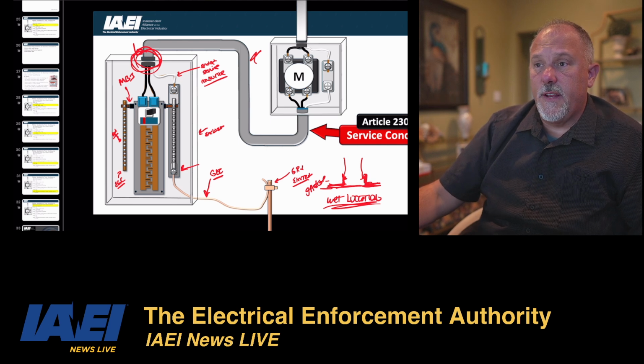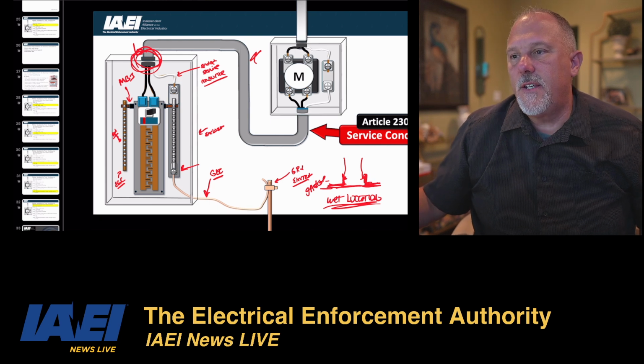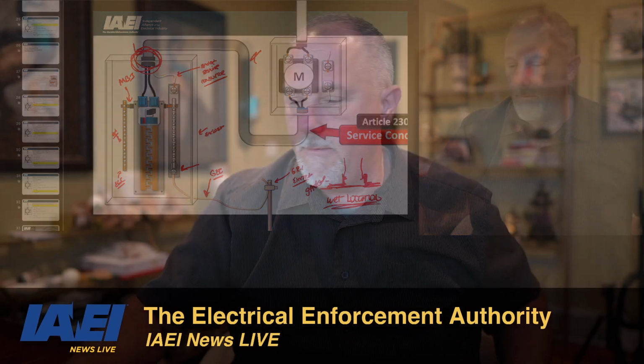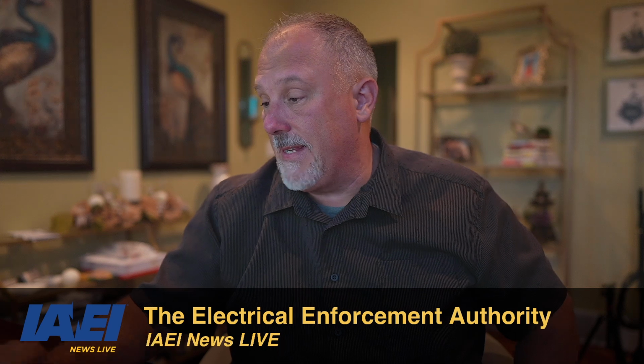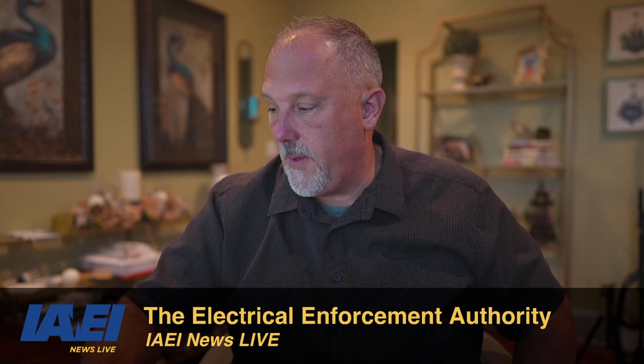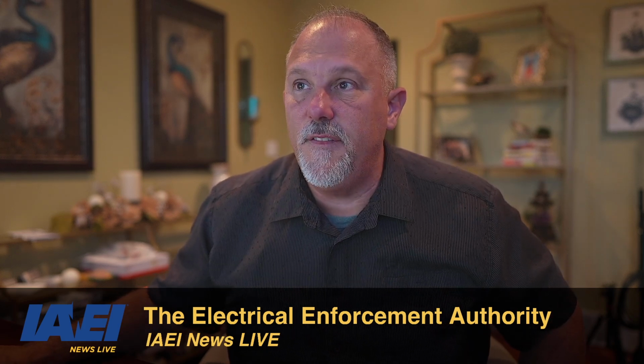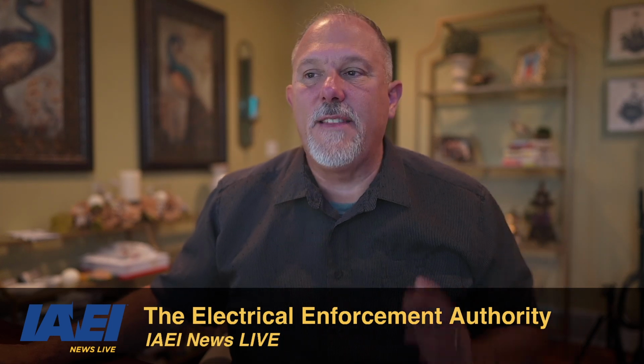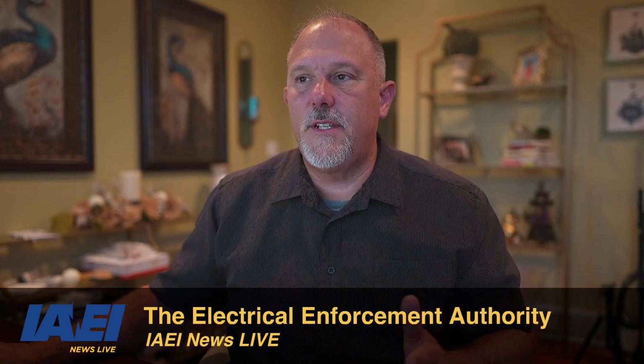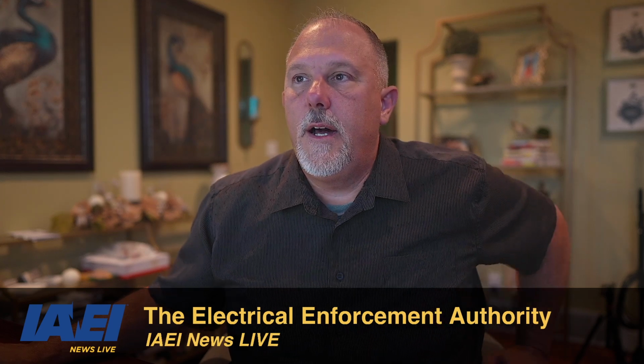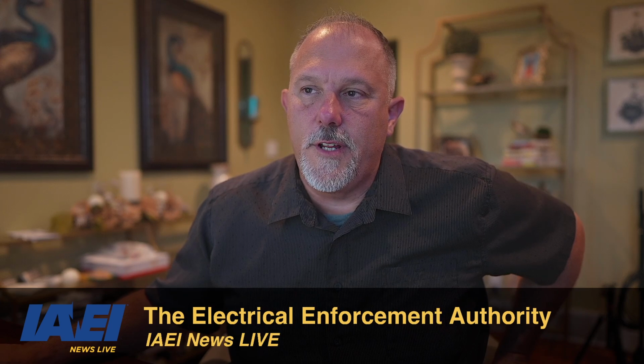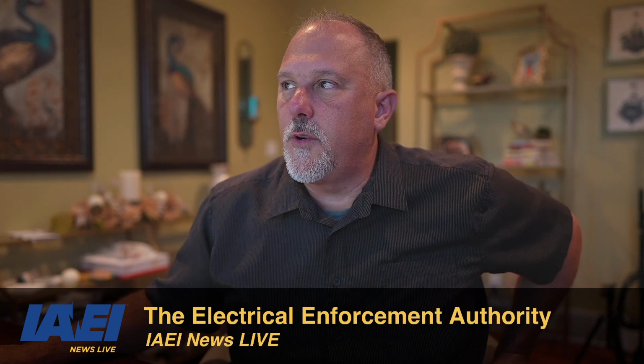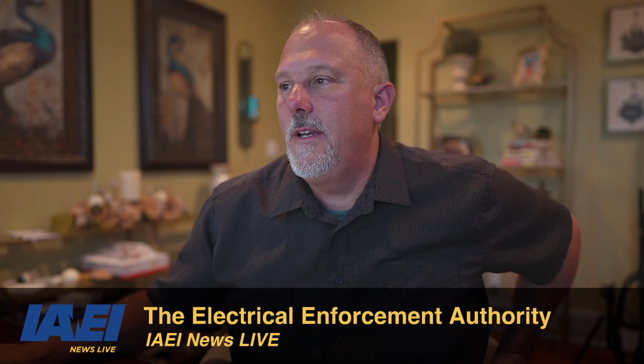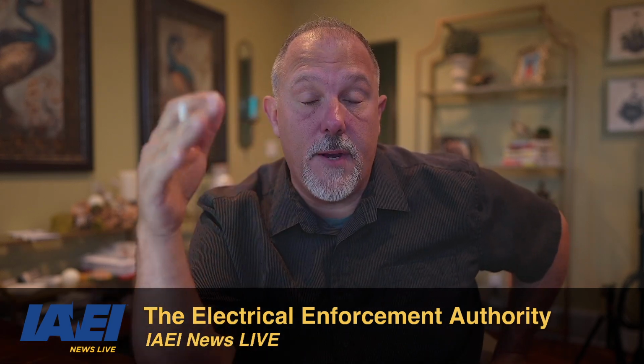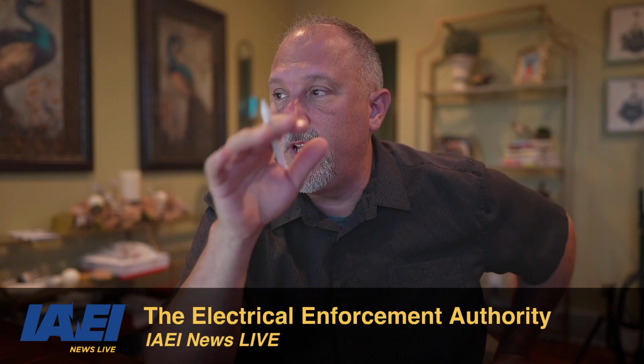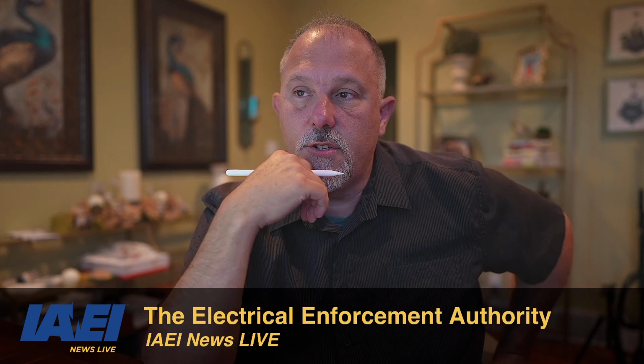See what else is in here. I'm trying to think what else I might have. So in any case, let's take a look at what I didn't cover, because we have our service equipment. That's Article 230, Part 5. You never would have thought that service equipment is this complicated, but it is. Part 5, service equipment enclosed or guarded. Energized parts of service equipment shall be enclosed. Again, you're going to buy listed equipment. Barriers are going to have to be in place. Even if it's listed equipment, the barriers aren't automatically installed. You're going to need to make sure those barriers are installed in your service equipment.